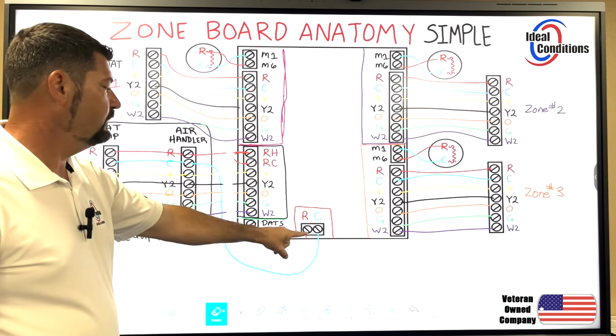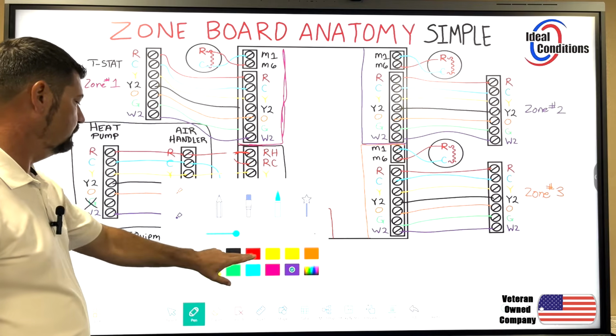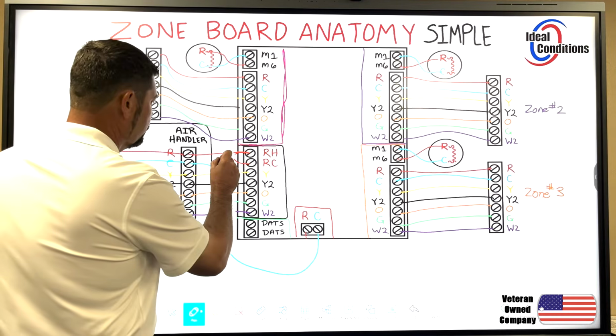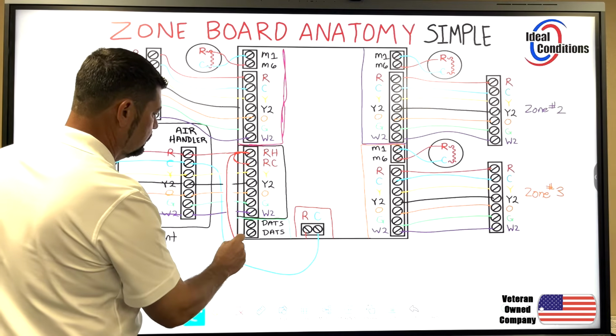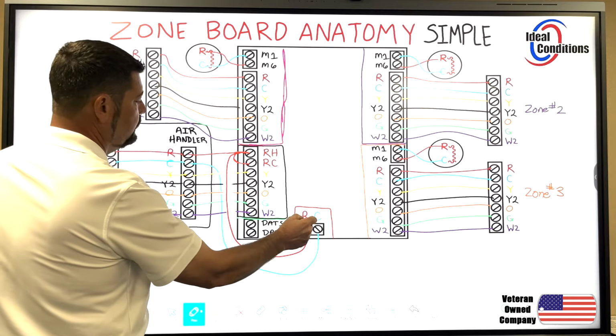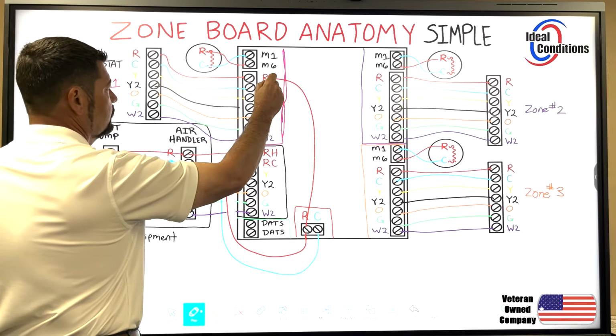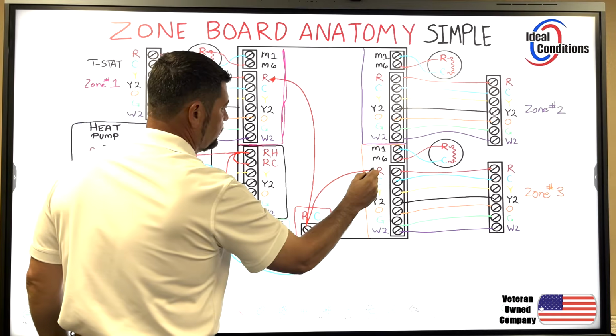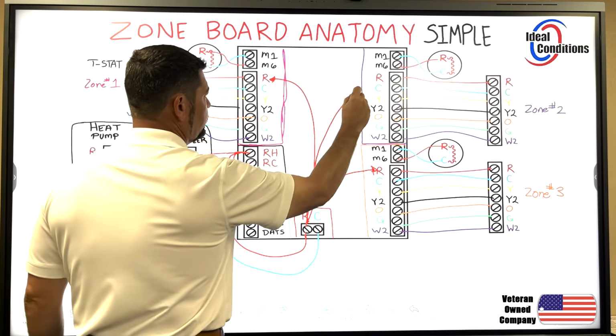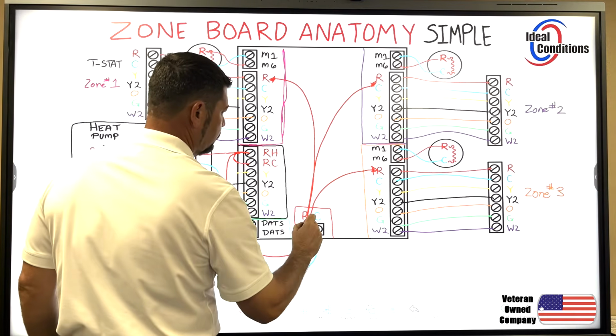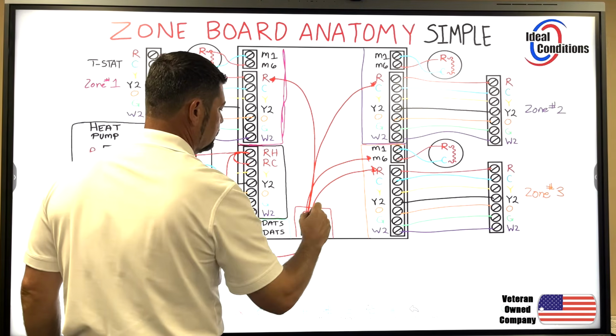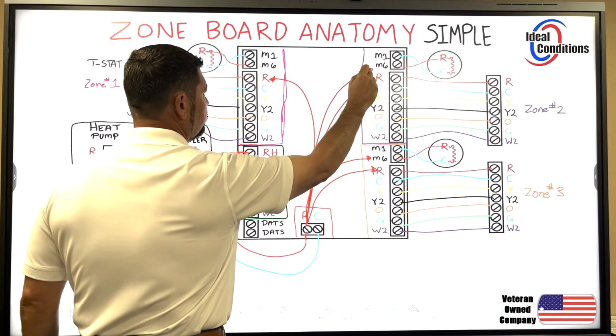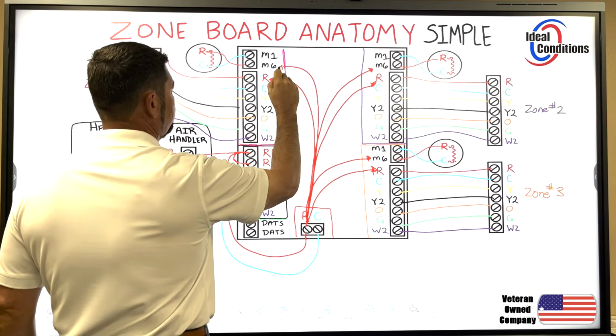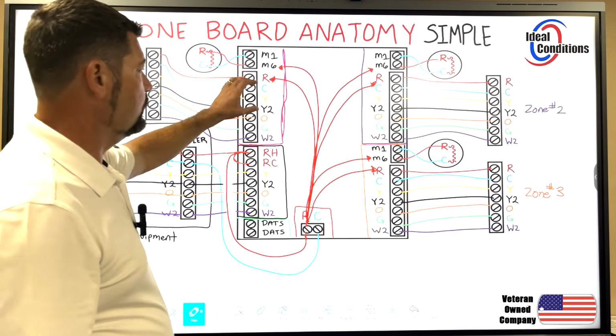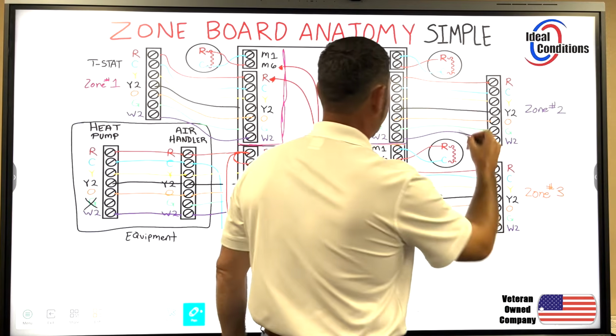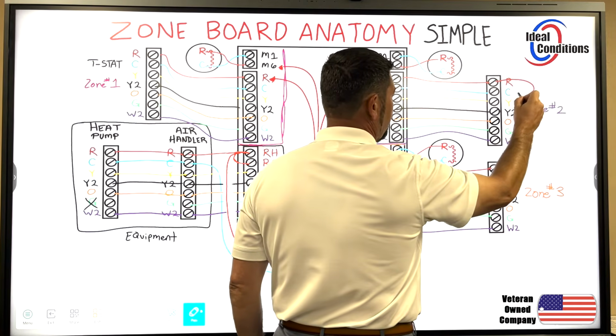All right, so by putting 24 volts here, let's go back to that one step. By putting 24 volts here, this 24 volts is now supplying power here. It's supplying power here. It's supplying power here. Okay, it's also supplying power on M6. It's sending power up here to this M6 when needed, and it's supplying power to this M6 here. All the rest of the power on these terminals is being relayed back from the thermostat. So if I need power on Y, well, red's just going to send power on Y.